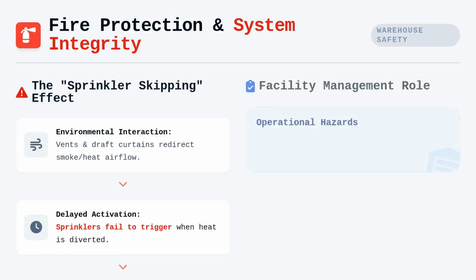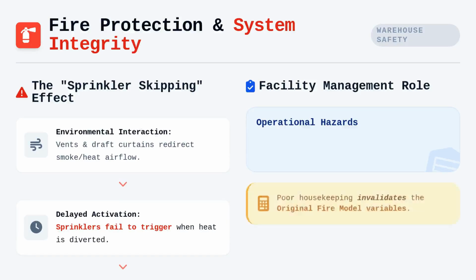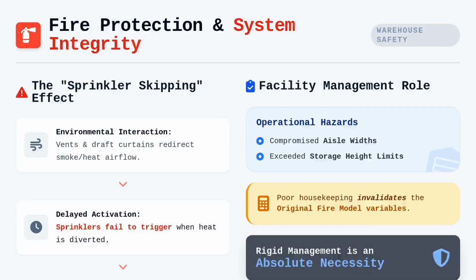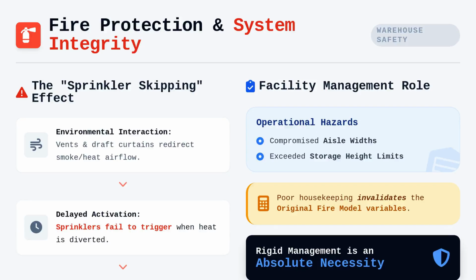Facility management plays a critical role here because even the best engineering design can be rendered useless by poor housekeeping. If aisle widths are compromised or storage height limits are exceeded, you have essentially changed the variables of the original fire model. Rigid facility management is not just a policy preference for the owner. It is an absolute necessity for the integrity of the fire protection system that you have designed.